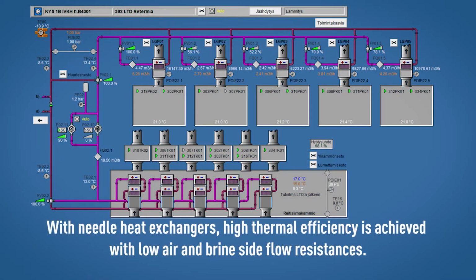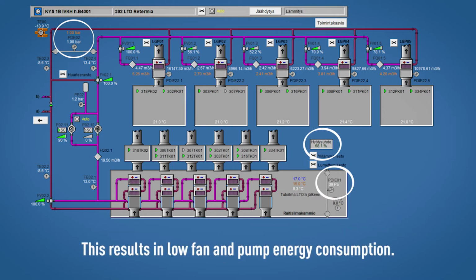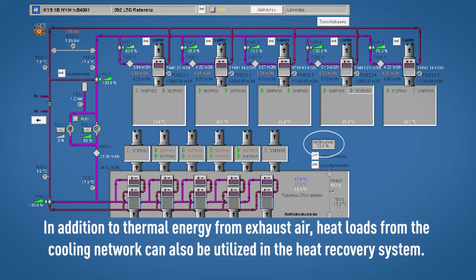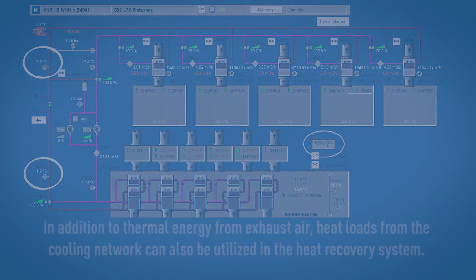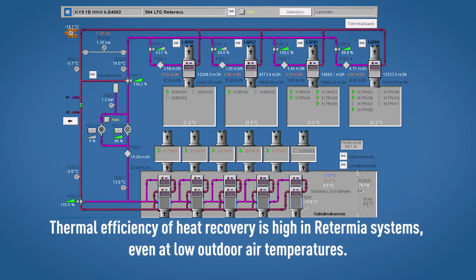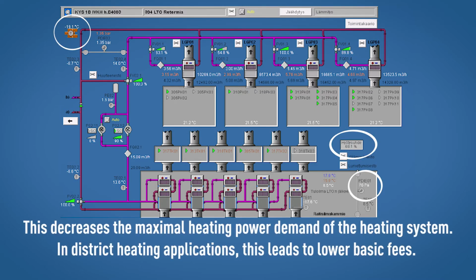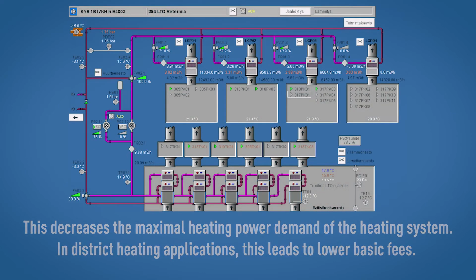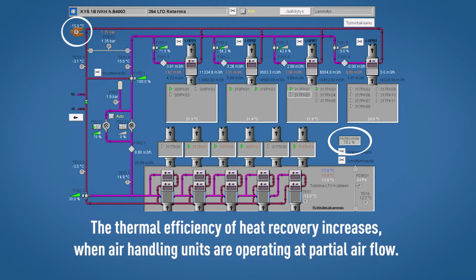With needle heat exchangers, high thermal efficiency is achieved with low air and brine side flow resistances. This results in low fan and pump energy consumption. In addition to thermal energy from exhaust air, heat loads from the cooling network can also be utilized in the heat recovery system. Thermal efficiency of heat recovery is high in Retermia systems even at low outdoor air temperatures. This decreases the maximal heating power demand of the heating system. In district heating applications, this leads to lower basic fees. The thermal efficiency of heat recovery increases when air handling units are operating at partial airflow.